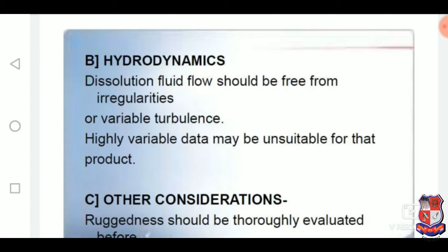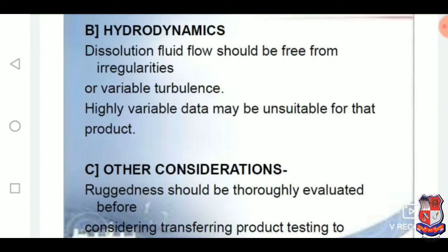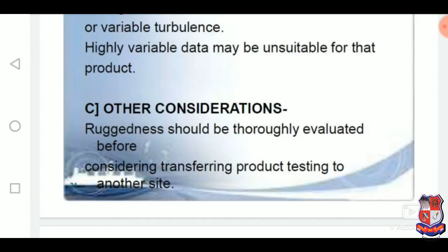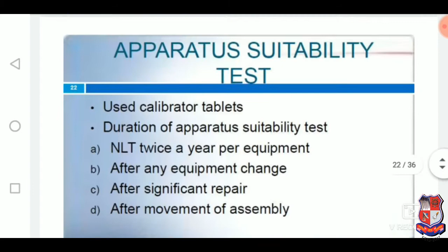Hydrodynamics: in that, the dissolution fluid flow should be free from irregularities or variable turbulence. Highly variable data may be unsuitable for that product. What are the other considerations? Ruggedness should be thoroughly evaluated before considering transferring the product testing to another site. Apparatus suitability test: in that, calibrated tablets are used, and the frequency of the apparatus suitability test is not less than twice a year per equipment, after equipment change or after significant repair, and after movement of the assembly.